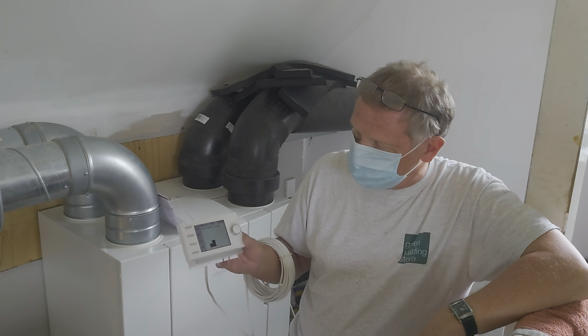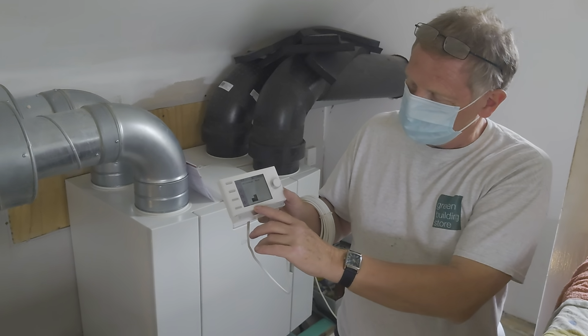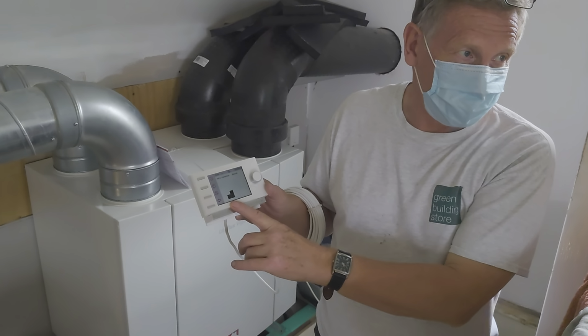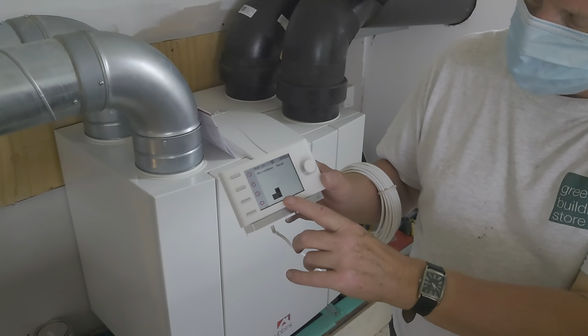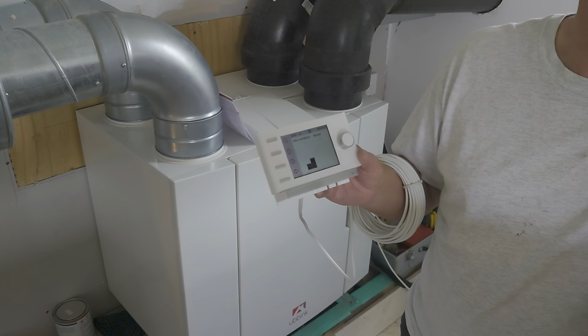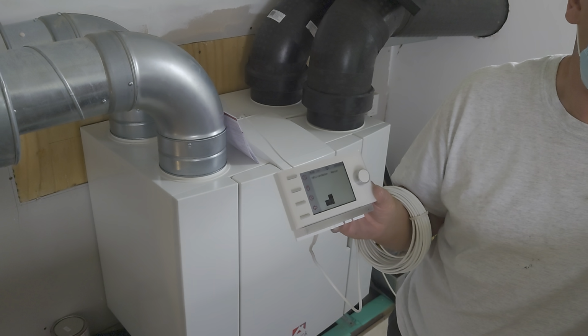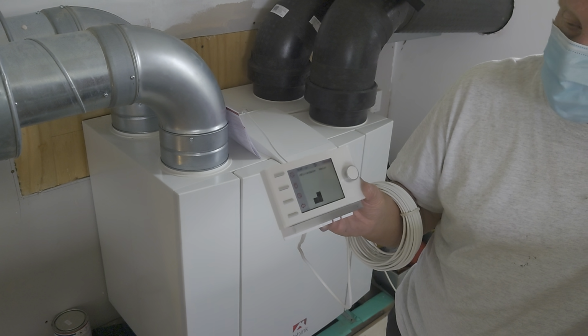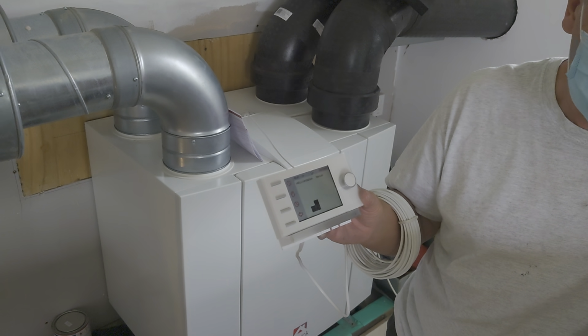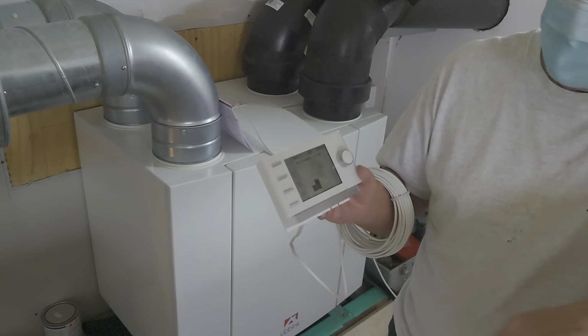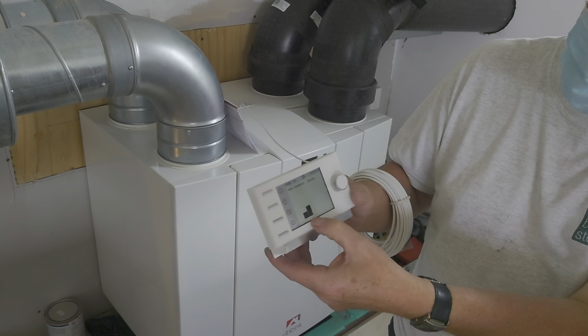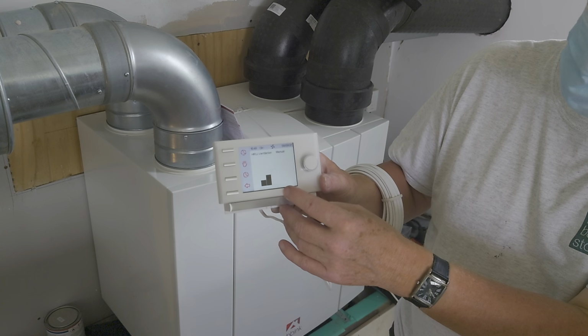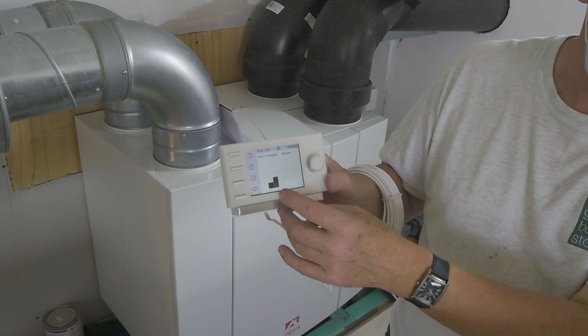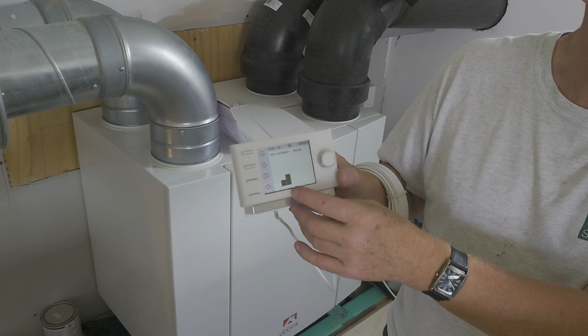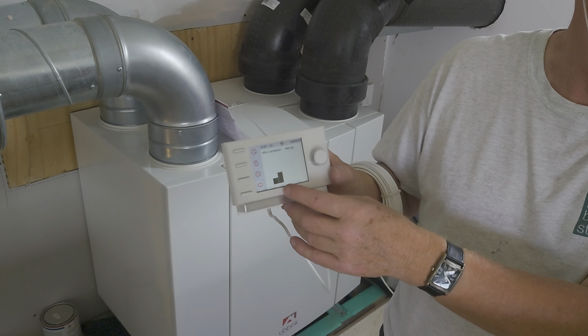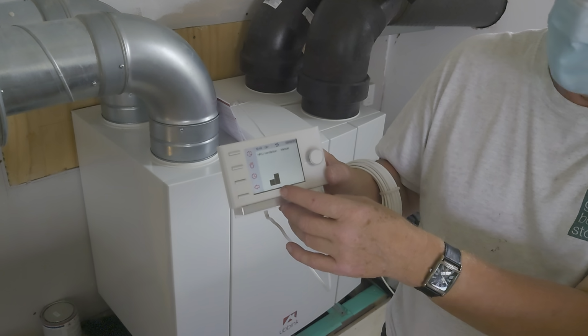So the first bar, you'll never use unless you're selling the house. The second bar, think of that as being holiday setting—what we refer to in the industry as fan speed 1. So it's 0, 1, 2 and 3. Fan speed 1 is holiday mode: you've gone away for a fortnight, nobody's in the house, you can drop the ventilation if you can remember to do it.